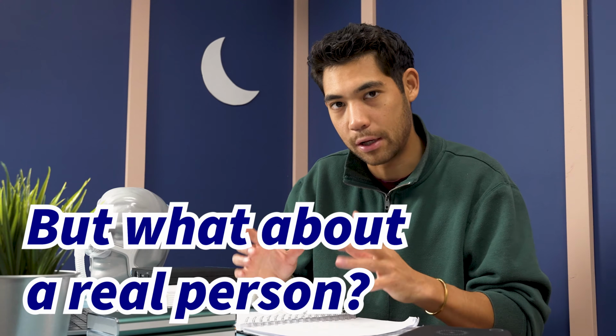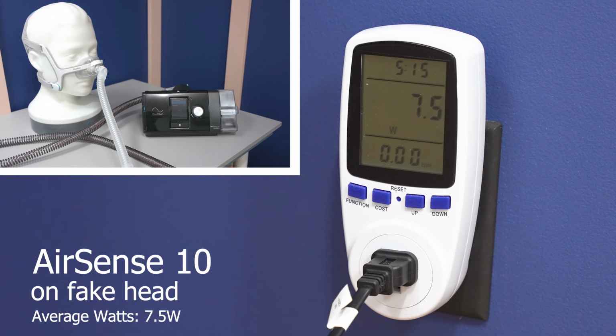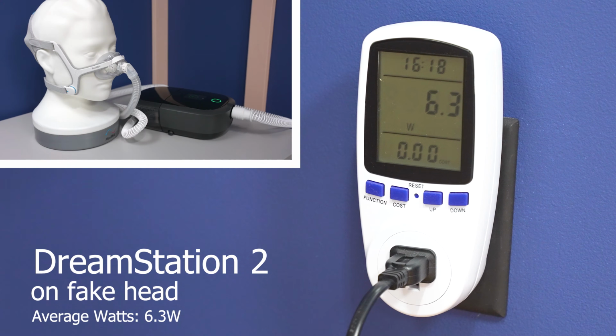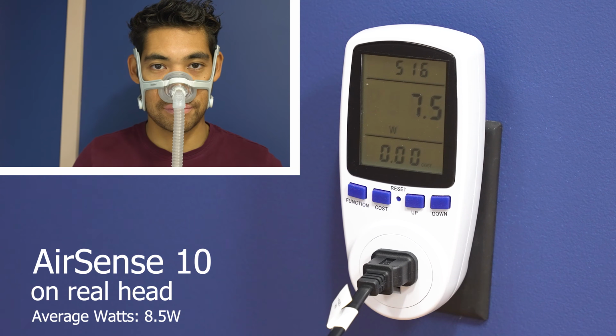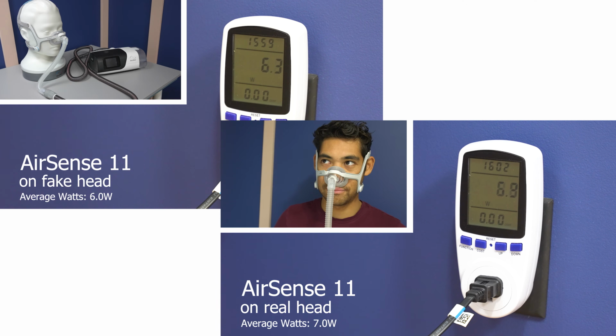To get a better idea of run times, we need to figure out how much a CPAP draws in terms of power on a real person. I tested each CPAP with a watt meter on both a dummy and a real person, myself. What I found is that a CPAP uses about 10 to 20% more power on a real person. According to my test results, the real estimated run times would be about 85% of the duration we got on the dummy.